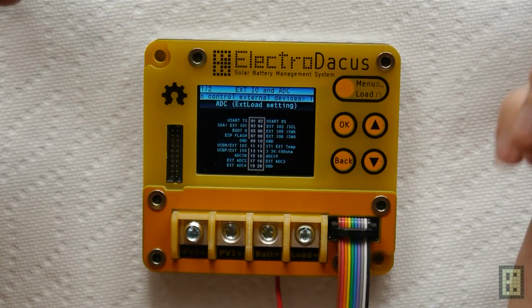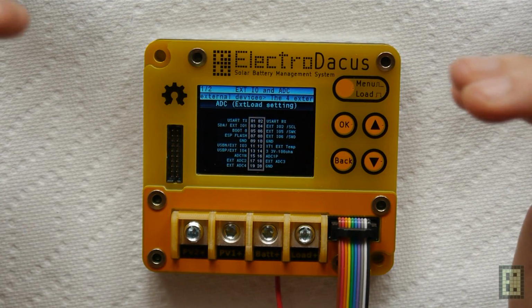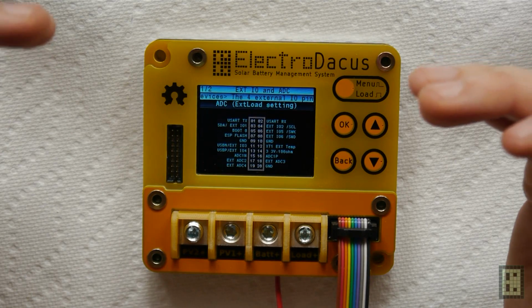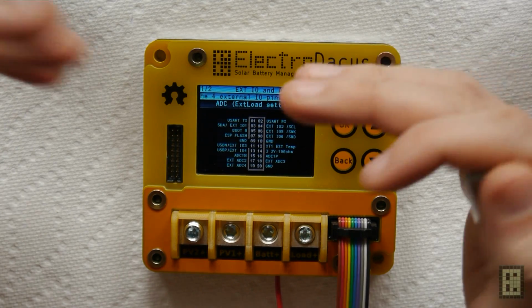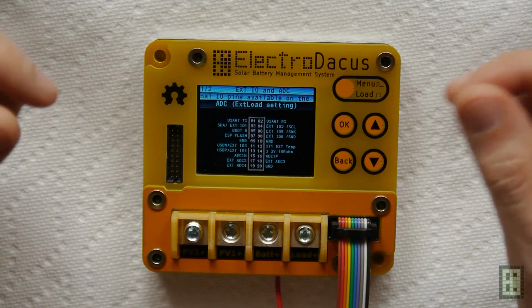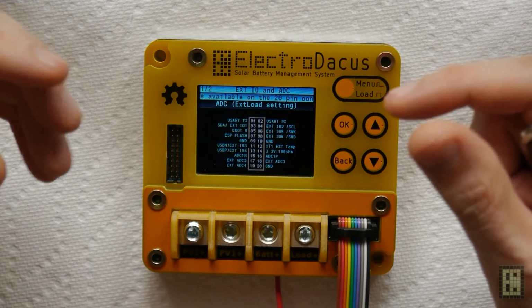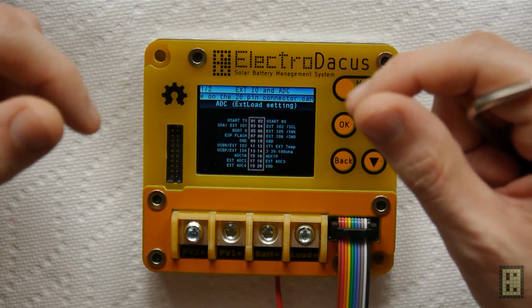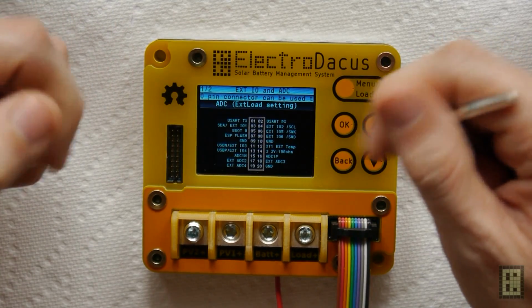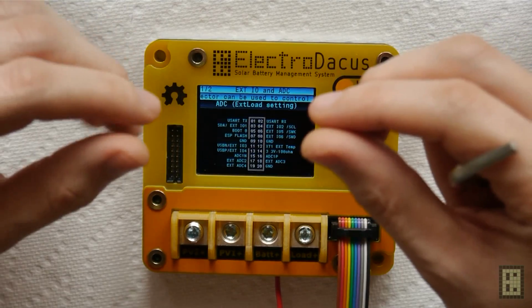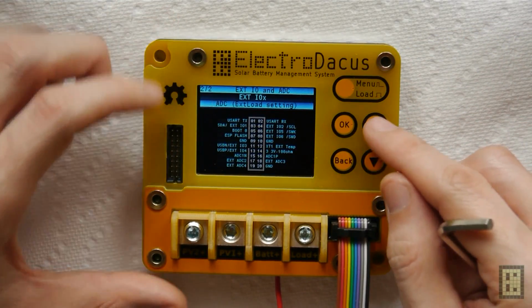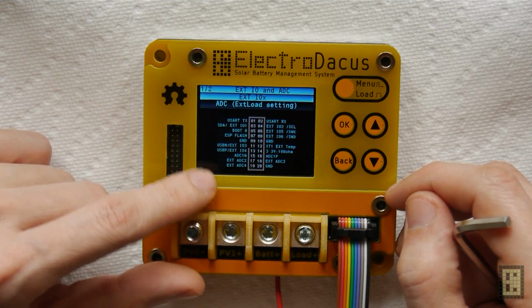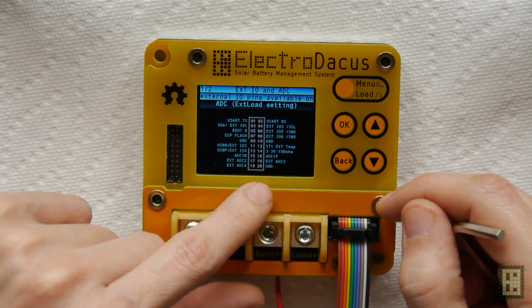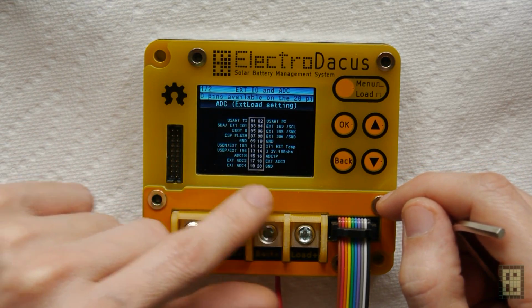You can use one that's rated up to 500 amps at 75 millivolts, meaning that when 500 amps go through that power resistor, 75 millivolts will drop across it, and that voltage drop is measured by the solar BMS on pins 15 and 16 here, ADC1N and 1P.